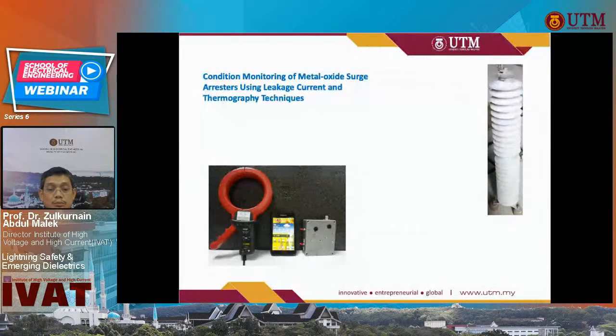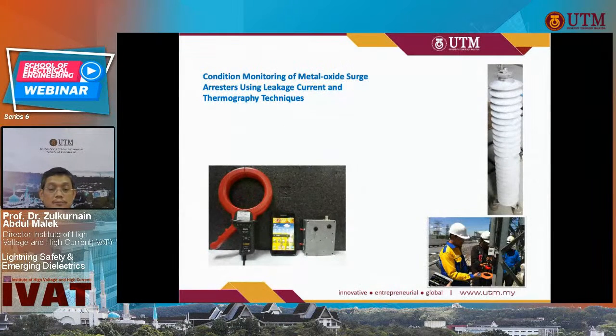The arresters need to be constantly condition monitored so that they work perfectly throughout their years. If they fail, you are exposing your transformer to damage as well. So at IVAT we have developed what we call a Bluetooth and web-based measuring system, so that we do not have to record manually and then go back to the station to key in the data.